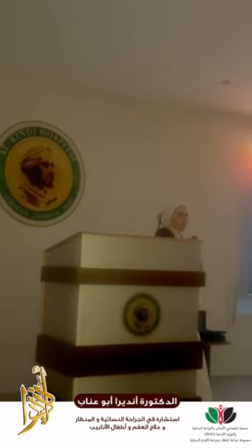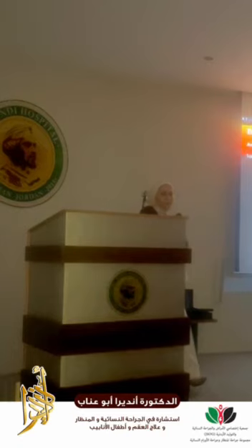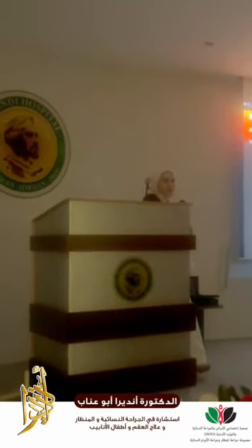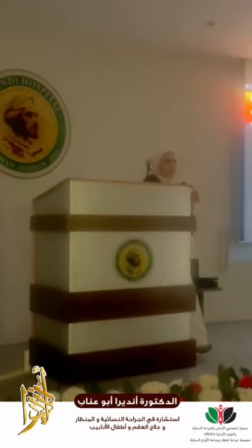What about monopolar and bipolar? In laparoscopic gynecology, monopolar is preferred to be used just for cutting, the cutting mode, because if used in the coagulation mode, it will not coagulate well. It will coagulate only a diameter of about 1 millimeter.